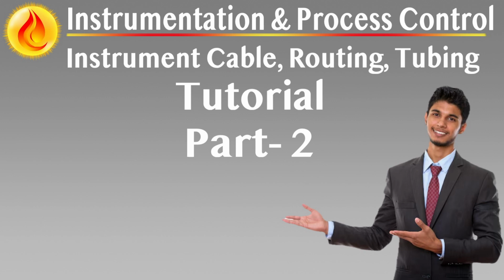Segregation supports both operational and maintenance convenience. Field-level segregation may be driven by system grouping, e.g. gas detection, process analyzers, instrumentation for specific units, while control room segregation ensures logical organization across marshalling panels, termination blocks, and system cabinets. Routing design for accessibility, safety, and EMC optimization.